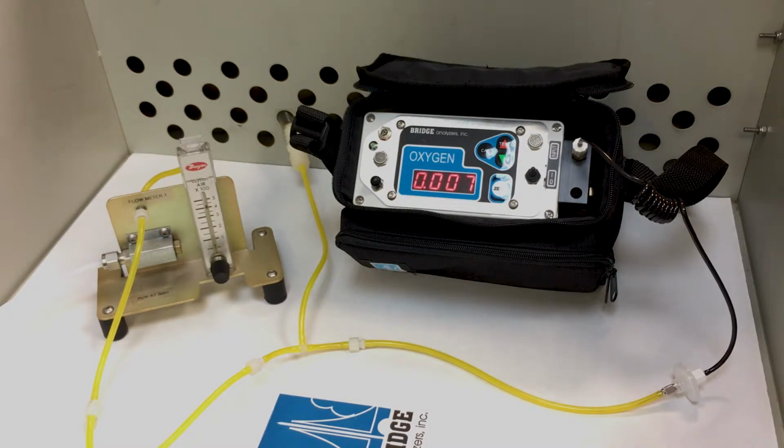And I'll just go ahead and leave it right there. So I'm at 0.006, and you'll see it'll probably tick down just a little bit more. It'll actually go negative as well, which would tell you you've calibrated probably a little too far. We tend to calibrate at around 0.03 to 0.05, allowing a little bit of extra tail there to allow these readings to keep coming down.